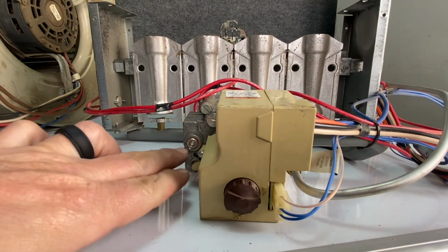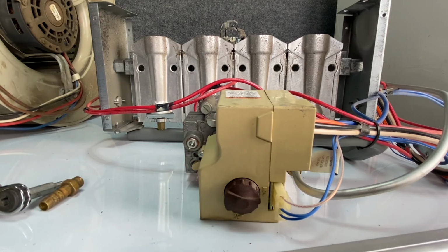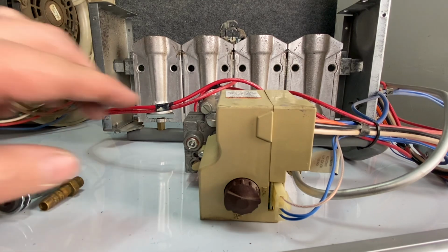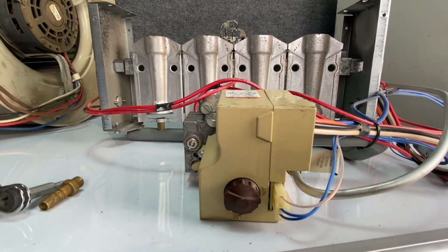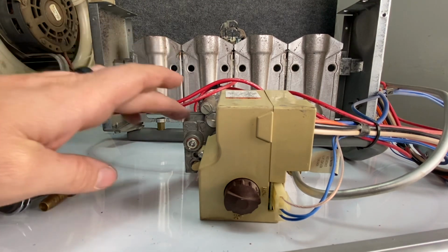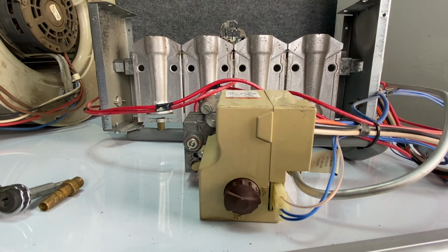Soap bubbles work as well. You can put the soap bubbles around there, but you want to make sure you use a specific type, because regular plain kitchen soap could have a corrosive effect on some of this aluminum. So make sure you use a gas leak detector solution designed for natural gas, and all the supply houses carry that.